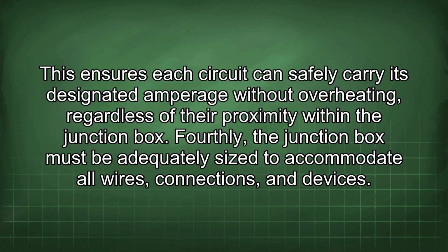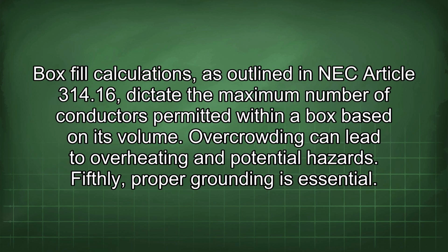Fourthly, the junction box must be adequately sized to accommodate all wires, connections, and devices. Box fill calculations, as outlined in NEC Article 314.16, dictate the maximum number of conductors permitted within a box based on its volume. Overcrowding can lead to overheating and potential hazards.